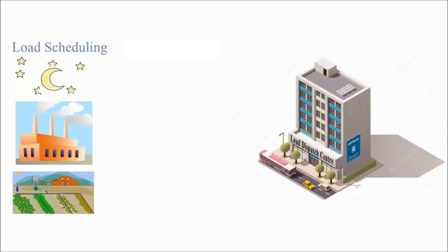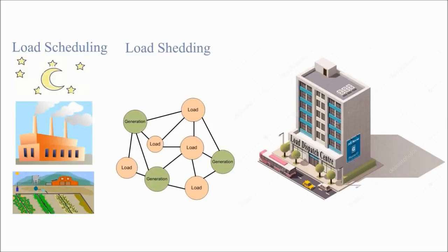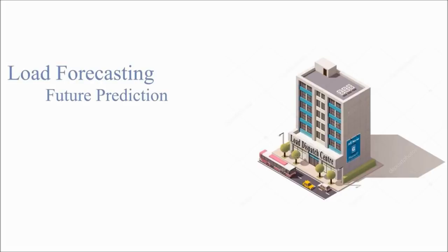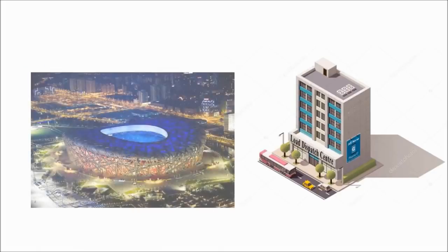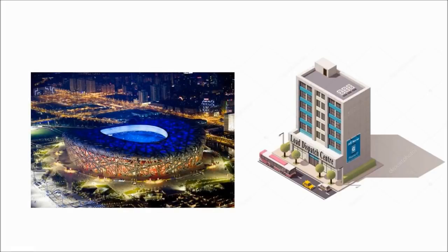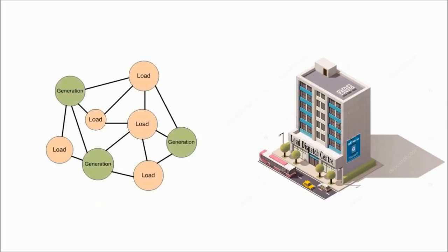In dry time, when there is a shortage of water in dams and rivers, meaning hydropower stations are not capable of generating the required amount of power, the center gives instructions of load shedding to the distribution companies. It means for different time slots, different categories of load have to be off. Also, it is the duty of the center to forecast the load demand by considering all possible future events in its periphery. For example, for a big sports event like the Olympics, it has to instruct the generating stations to ensure a reserve of energy for any peak demand.